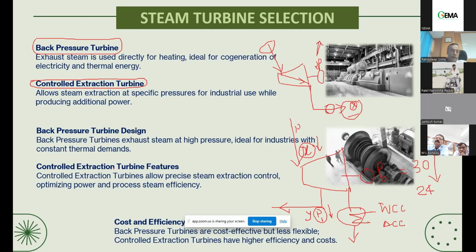However, for an extraction turbine, we talk about a controlled extraction turbine. In a controlled extraction turbine, there is a control valve integral to the steam turbine. Up to a certain level, say up to 25-30% of the load, whatever your power demand, whether it's going down or not, your pressure is not going to change, it will remain constant. That is called a controlled extraction steam turbine, used in process industry.